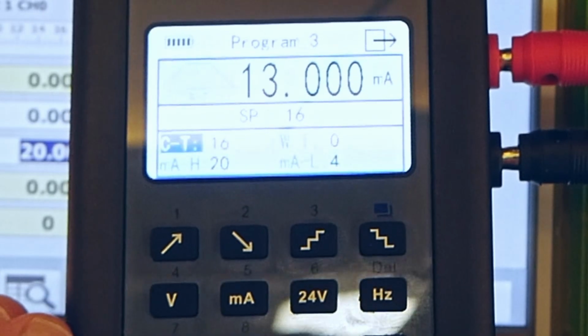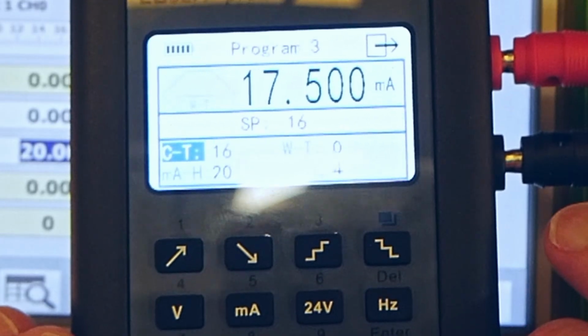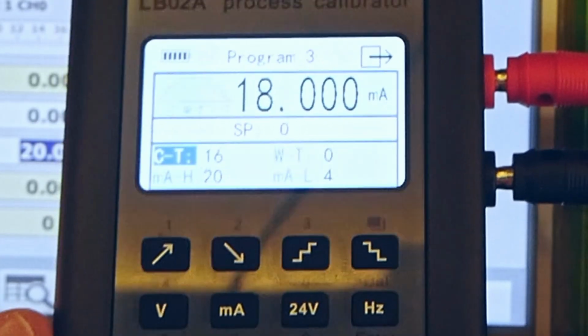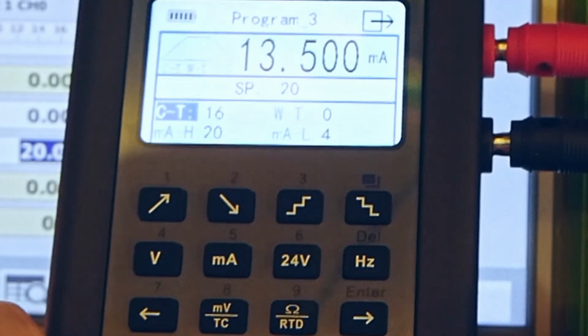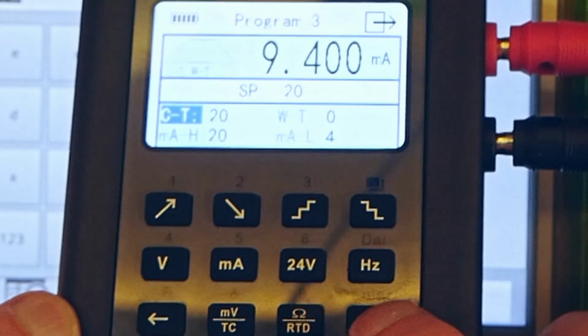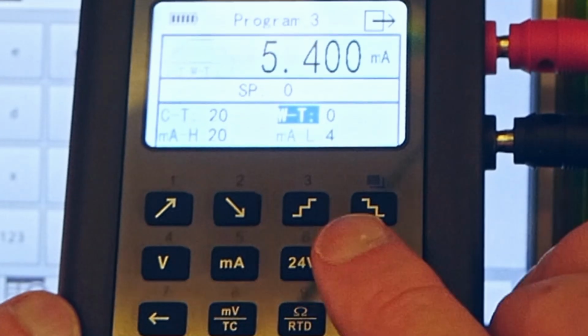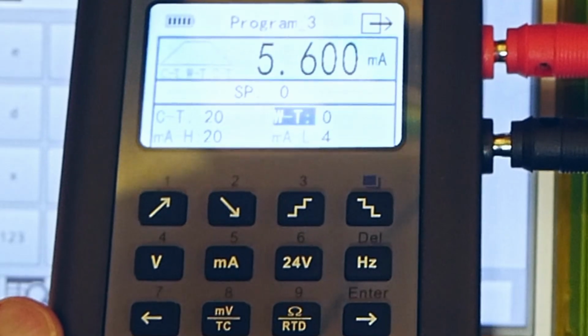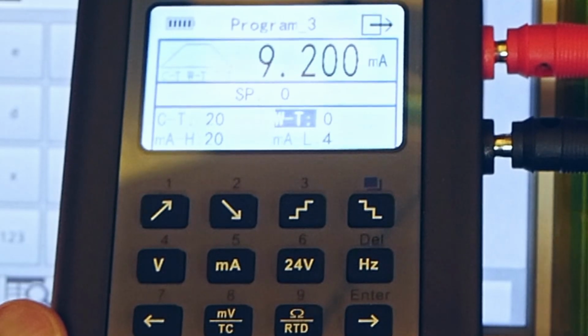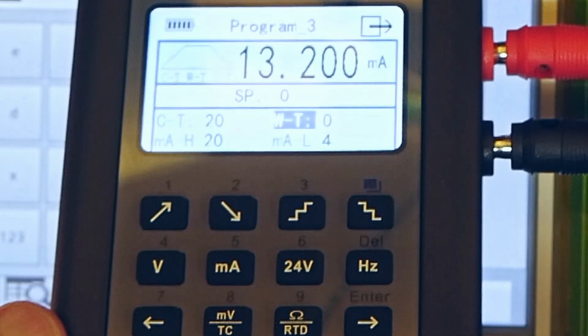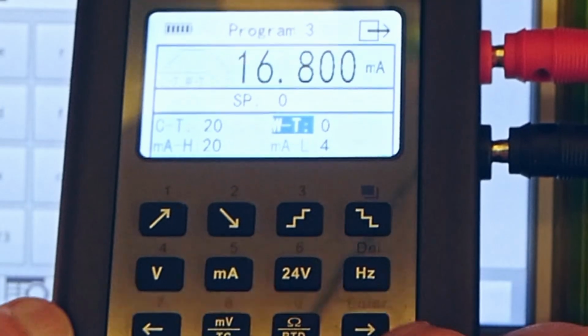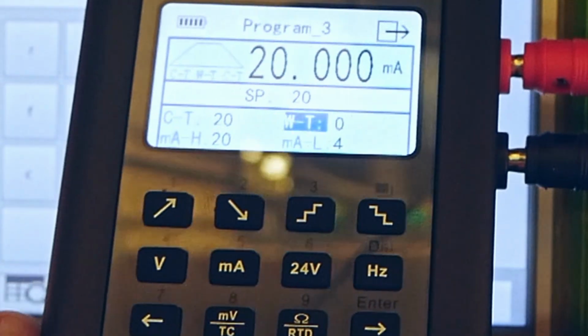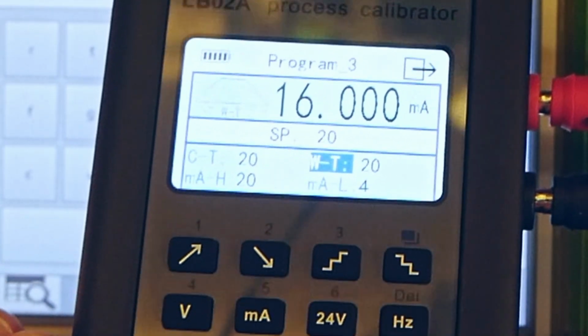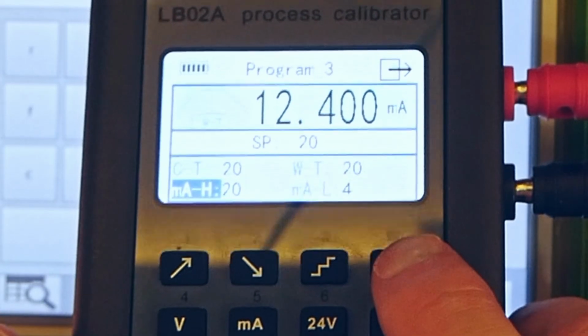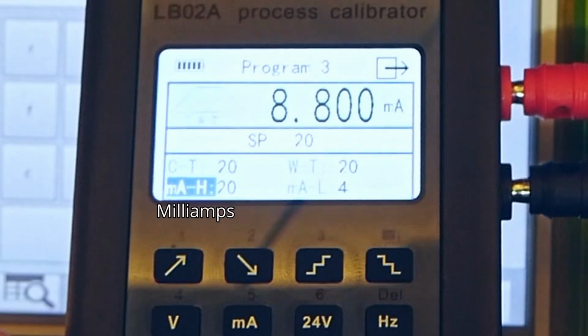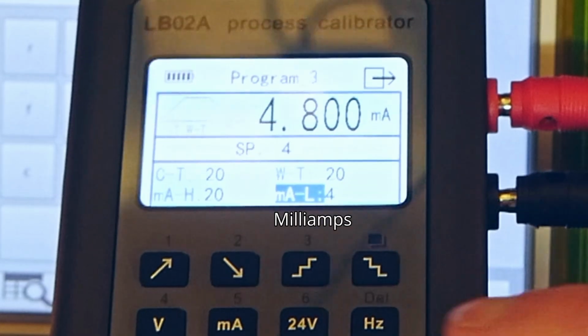So right now it's 16. I, let's say, want to change it. I delete the value and I will change it to 20. I will enter it. And then there is this WT. That means when set point high limit or low limit reached, how long it will stay there. So I will set it also to 20 seconds. And we can change milliamp high limit, so right now 20, and milliamp low limit, right now 4.